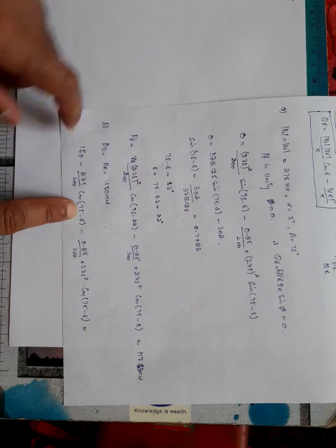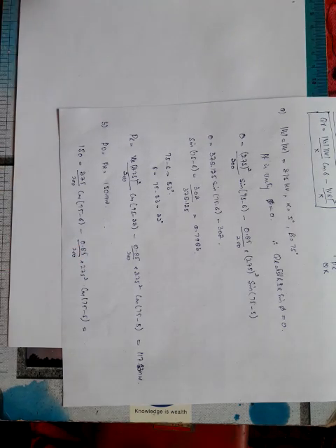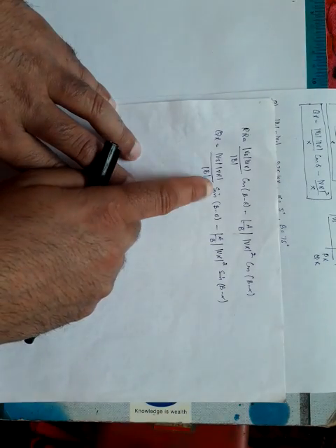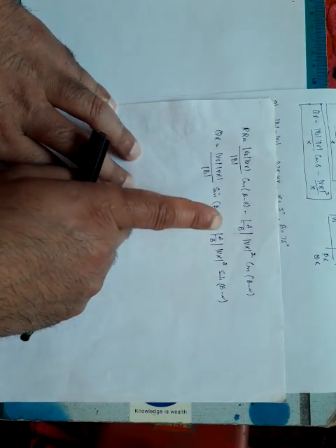In the second case, the power demand has increased. This is the power demand, 117 megawatts. Now power demand has to be increased to 150 megawatt, and we need to calculate the value of what? The value of reactive power first. Since again for reactive power, you can see Vs is given, Vr is given. In this case also voltage profile has to be same. That means Vs is equal to Vr is equal to 275.